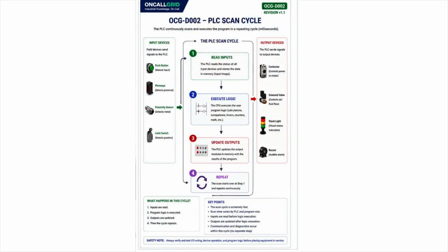And here's why that speed actually matters out on the floor. A PLC runs through its entire scan in just a few milliseconds. So a lot of what gets called an intermittent fault isn't the PLC being slow, it's loose wiring or a flaky sensor. The PLC is almost never the bottleneck. Quick fact for you. A PLC with a fast scan time can run through its whole program hundreds, sometimes thousands of times a second. That's fast enough to catch a sensor change quicker than your eye could ever register it.